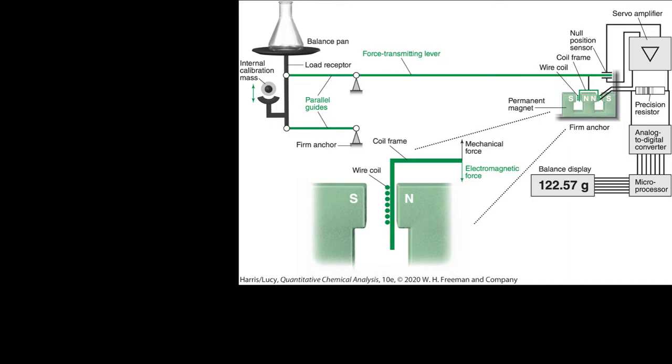And it does so until the null position sensor indicates that you're back in the normal null position. And this input necessary to balance things out, to make sure the electromagnetic force is balanced by the mechanical force coming from the weight of the object, is converted using an analog to digital converter. So in the analog world, everything is continuous, but in the digital world, we need to change things into ones and zeros. And this is ultimately read by a microprocessor and displayed and calculated on our balance to say, in this case, 122.57 grams, which wouldn't actually be very sensitive at all for an analytical balance.